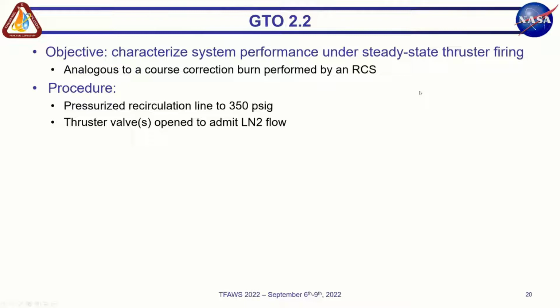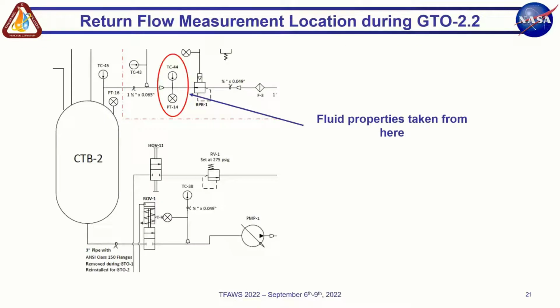Moving on to the next test objective, GTO 2.2, we wanted to characterize system performance under steady state thruster firing. The driving case for this would be a course correction burn performed by an RCS. It's some steady level of thrust over some predetermined amount of time, and we want to simulate that in our little hardware analog here. One thing to note, this is a zoom in from our schematic earlier. We used the data from these two instruments just downstream of our back pressure regulator to get our fluid properties for this test.